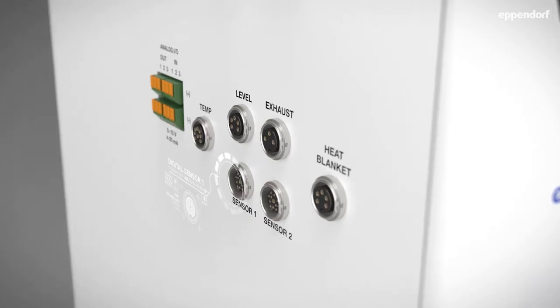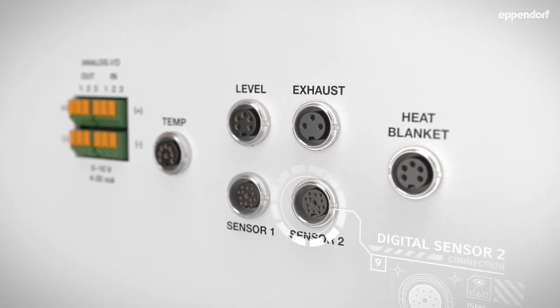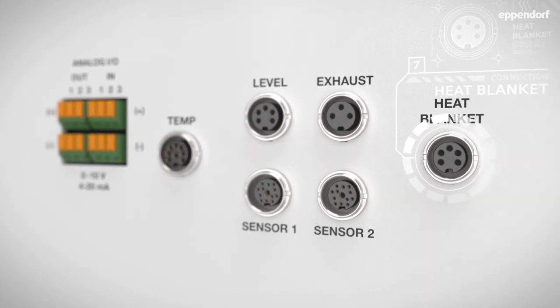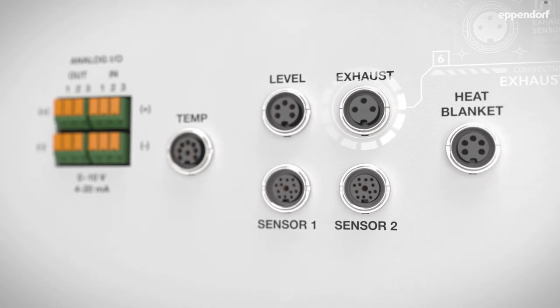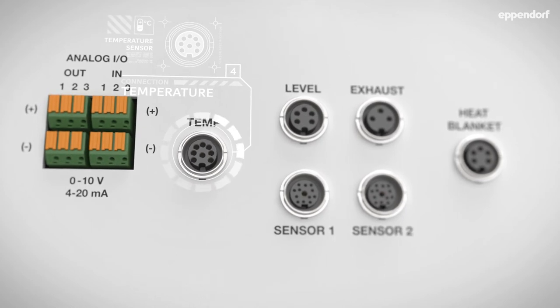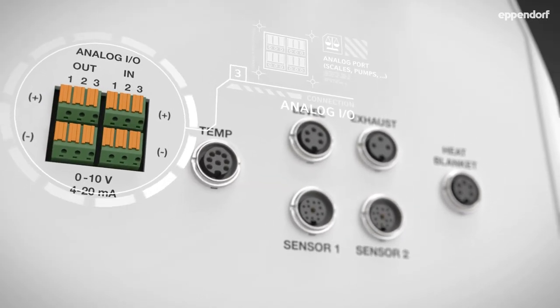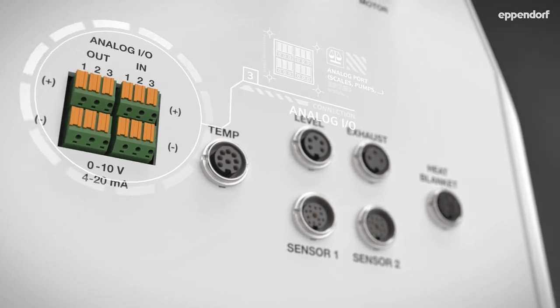Universal sensor connections with Mettler Toledo's integrated ISM platform give added flexibility for process control and feature pre-run diagnostics that can prevent in-process sensor failures. On the advanced model, three user-defined analog input-output connections allow you to integrate ancillary equipment like external variable speed pumps.